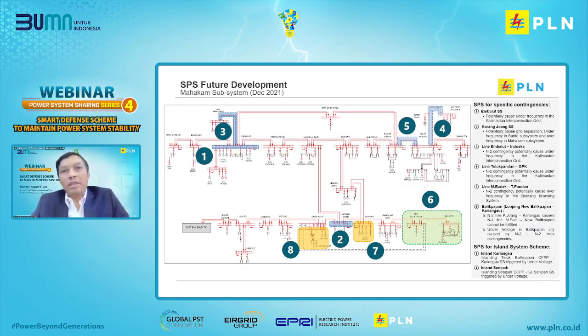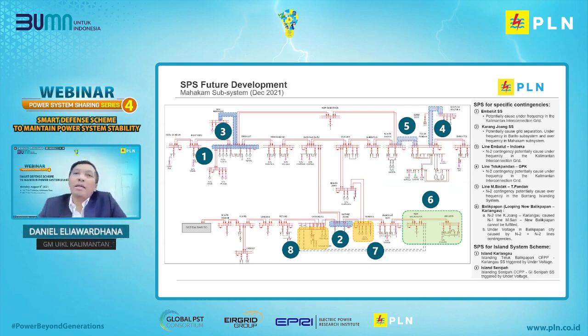The development of the system, such as additional substations, as well as increasing consumer load, will change the Kalimantan interconnection system. The following are the results of our scanning for potential disturbances in the Mahakam subsystem that have a major impact on the system. We have already scanned the possibility of 8 risks in the interconnection system. We will install 8 SPS development plans in the Mahakam subsystem, with 6 schemes to overcome contingency constraints and 2 schemes for island operation scenarios.